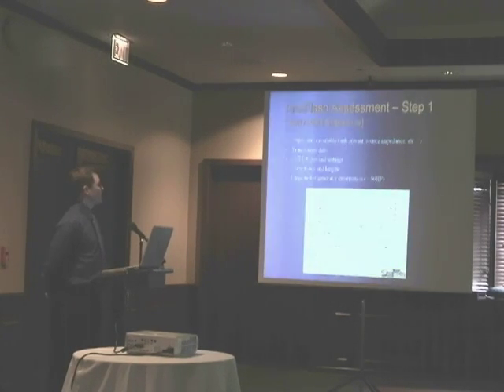All right, I'm going to go through our arc flash assessment now. This is step one. The first thing we're going to do in an arc flash assessment is to verify plant single lines. To do this, we need the utility info, the transformer data, the OCPD types and settings, cable types and lengths, and large motor and generator information. That includes anything over and including 50 horsepower. If the single lines are not good, sometimes it's a good idea to get those corrected before starting an arc flash assessment.